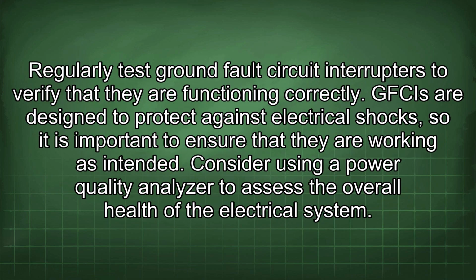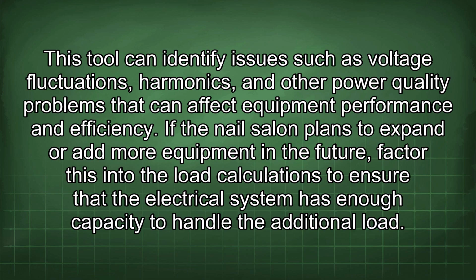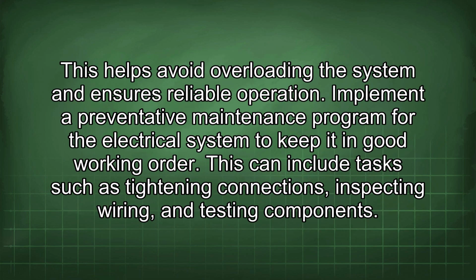Regularly test ground fault circuit interrupters to verify that they are functioning correctly. GFCIs are designed to protect against electrical shocks, so it is important to ensure that they are working as intended. Consider using a power quality analyzer to assess the overall health of the electrical system. This tool can identify issues such as voltage fluctuations, harmonics, and other power quality problems that can affect equipment performance and efficiency. If the nail salon plans to expand or add more equipment in the future, factor this into the load calculations to ensure that the electrical system has enough capacity to handle the additional load. This helps avoid overloading the system and ensures reliable operation.